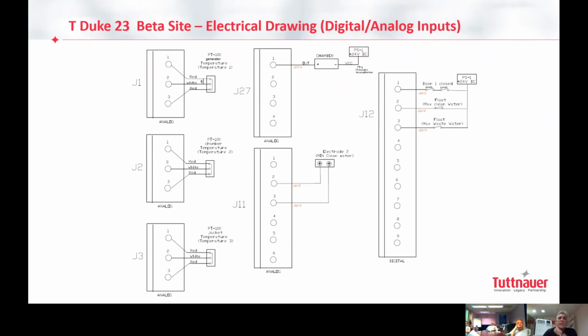The connection of the PT100: we have one for the steam generator, one for the chamber temperature, and jacket temperature. And we have here the 4 to 20 milliamp pressure transducer for the pressure. The electrodes and the float switch and door. Electrodes means there are two electrodes with a distance of 1 centimeter between them.